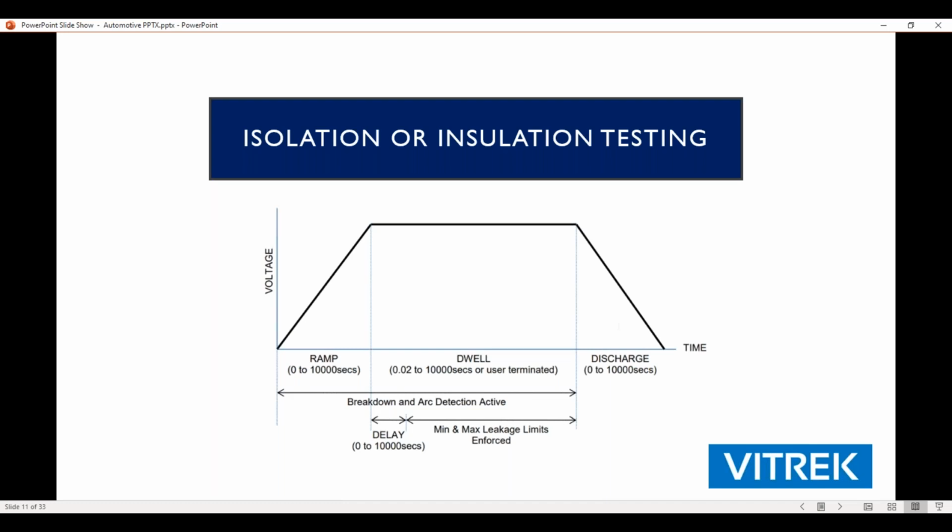Like I said, there are two sides of this. There are things that are supposed to be connected and things that are not supposed to be connected. The way that we identify things that are not supposed to touch and be isolated from one another is with an insulation resistance test, or a DC HIPOT test, typically at this voltage. It's a very simple test. You're going to have two conductors with an insulator in between them. One of those conductors could be the chassis of the vehicle. One of them is going to be, let's keep it simple, your 12-volt positive terminal coming off the car.